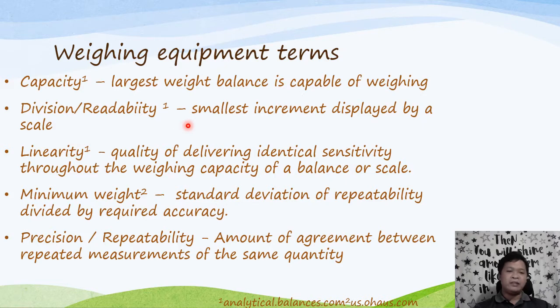Linearity, on the other hand, is the quality of delivering identical sensitivity throughout the weighing capacity of a balance or scale. One way to test this is by weighing two objects separately, each of which is approximately around half of the capacity. And then you weigh these together and yung weight nila separately when added should equal the weight kapag parehas silang nasa balance. No? So that is to say, at halfway through the scale, does it measure the same proportional mass as the as both of the objects combined?